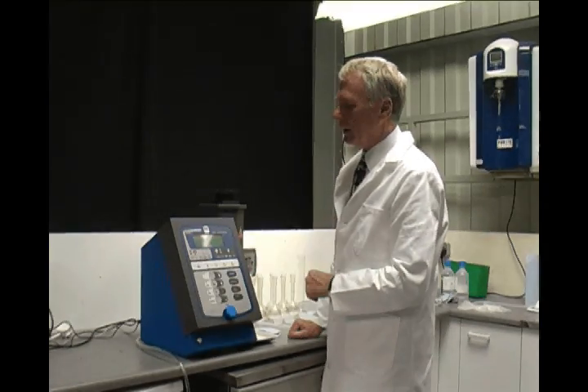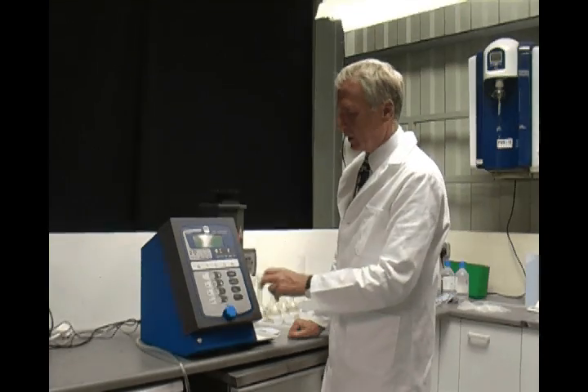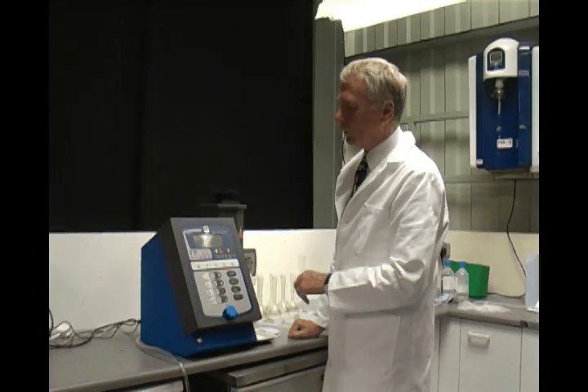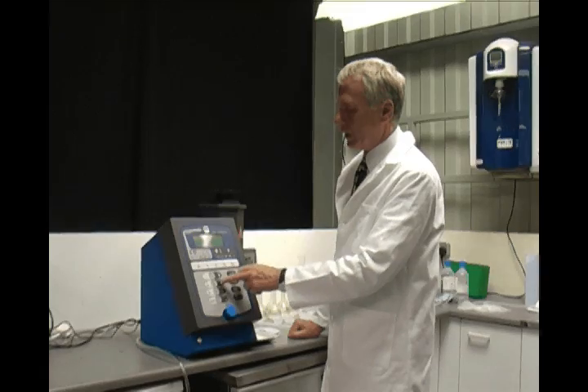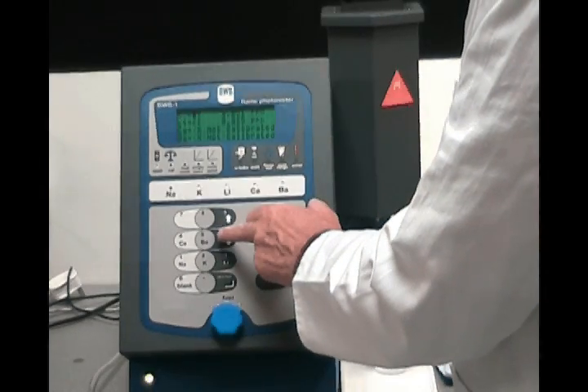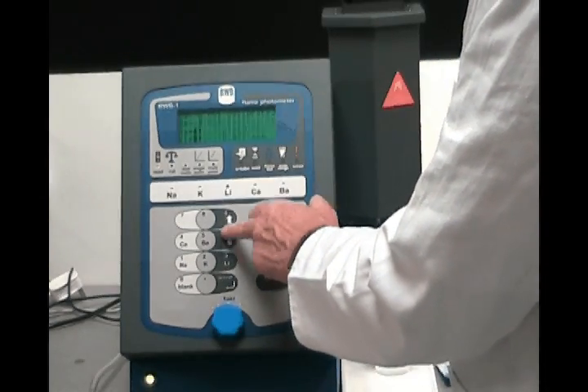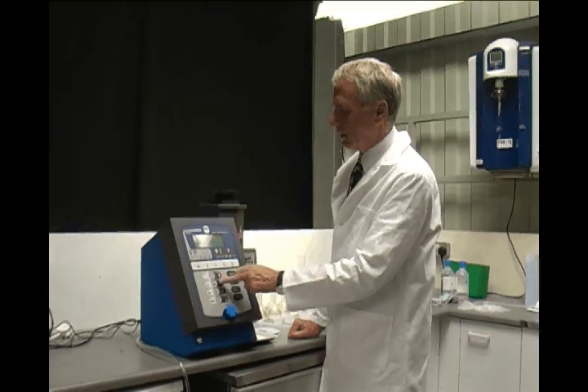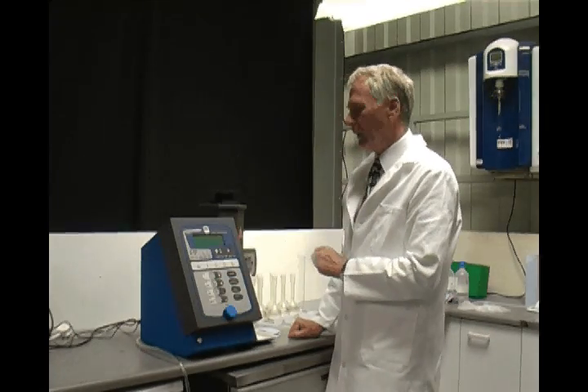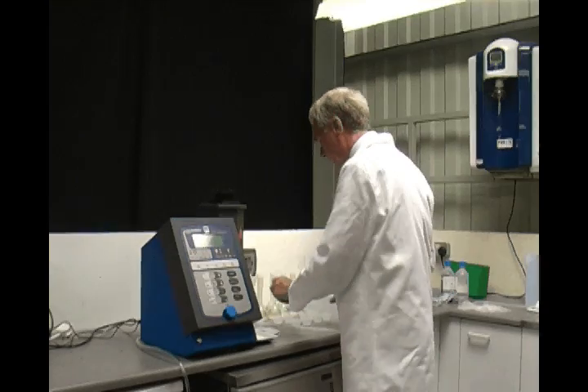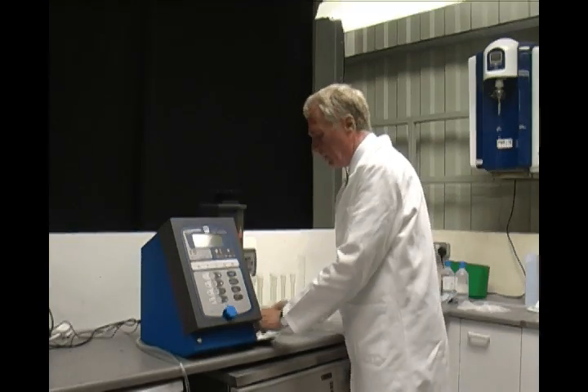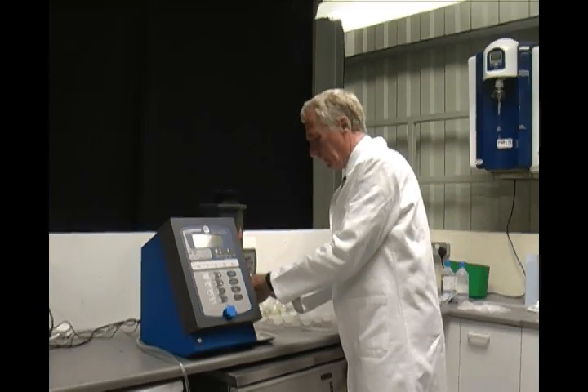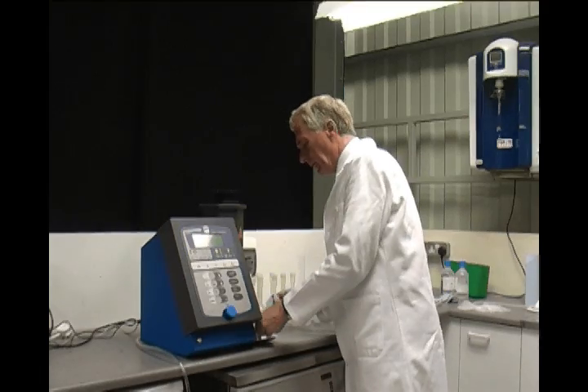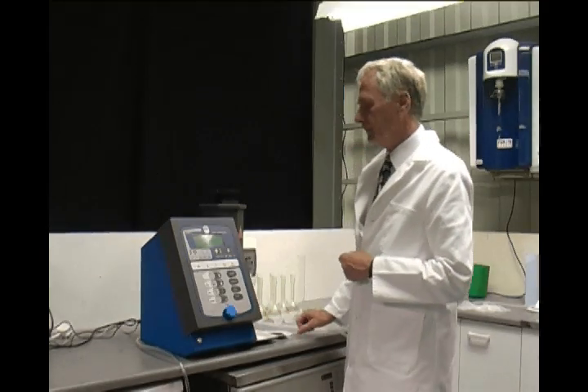It will also tell us that calcium is not calibrated. There are only 4 ions displayed at any one time, but you can select which 4 you want by using the scroll button to display 4 out of the 5 ions. I'm now going to go back to my 10 ppm sample that I used for calibration. Just have a look and see what it's reading.